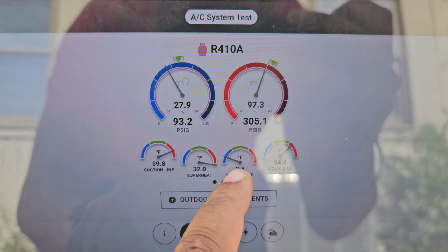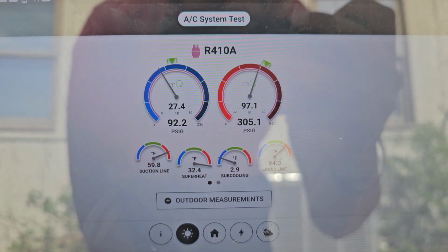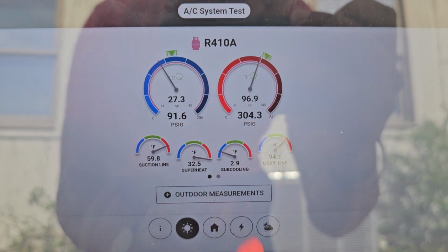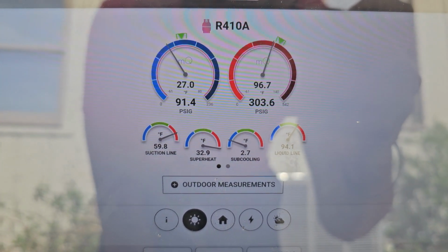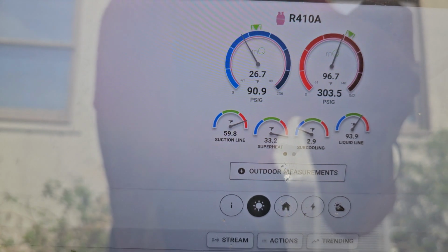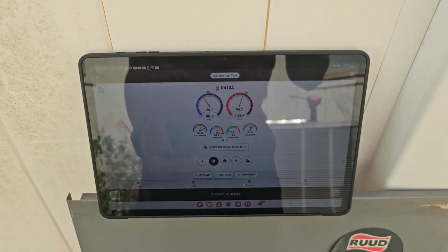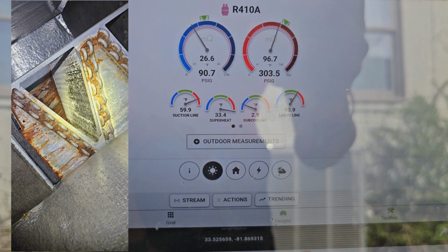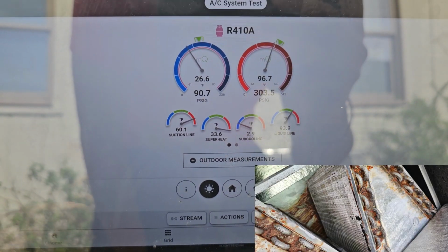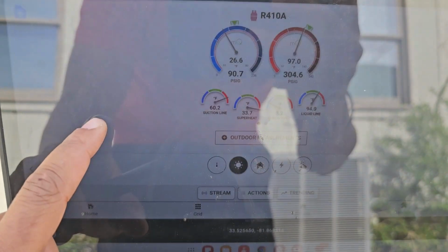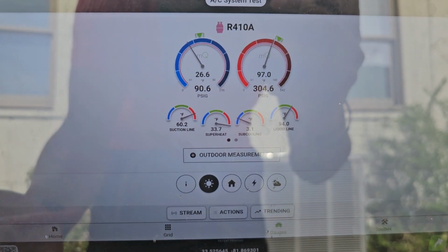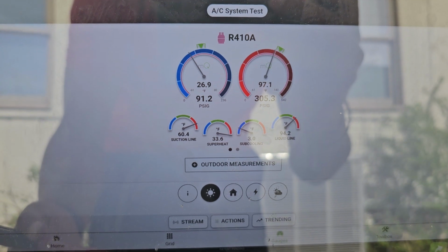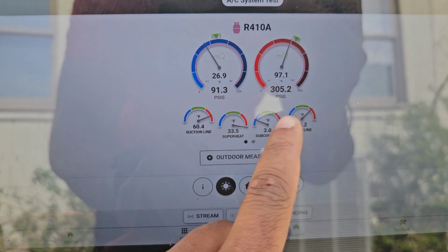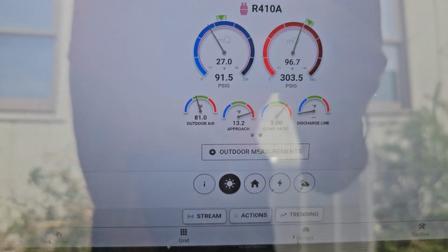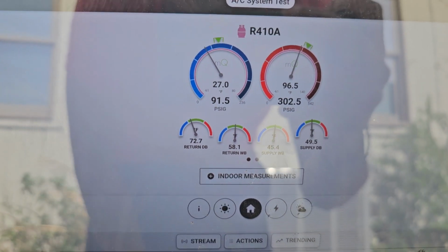As well, if you had a TXV, with how hot it is outside, that's definitely too low of subcooling. So with how old this system is, I could probably show you a picture of what the evap coil looked like before and after, but there's a good substantial amount of rust on the elbows and everything. There was a little bit of growth on the coil that I was able to clean off, but from what I'm seeing right now, I think this unit has a low charge.